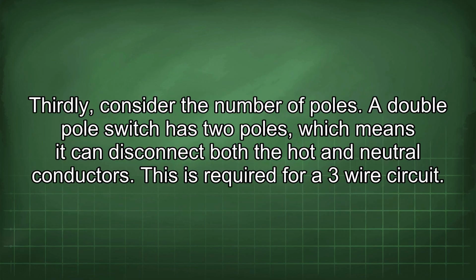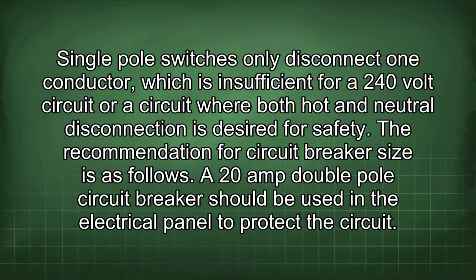Thirdly, consider the number of poles. A double-pole switch has 2 poles, which means it can disconnect both the hot and neutral conductors. This is required for a 3-wire circuit. Single-pole switches only disconnect one conductor, which is insufficient for a 240-volt circuit or a circuit where both hot and neutral disconnection is desired for safety.